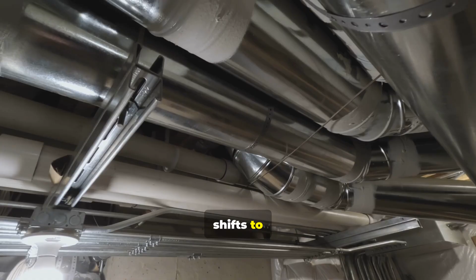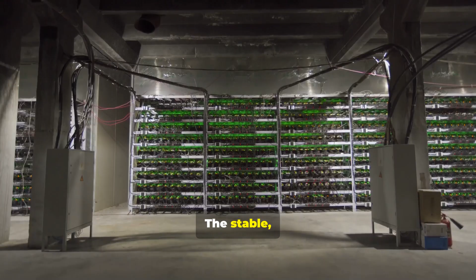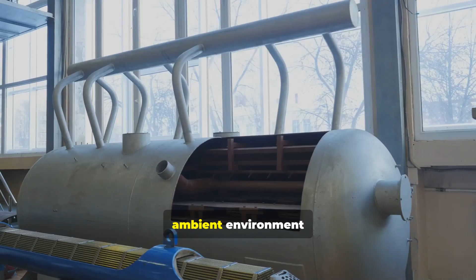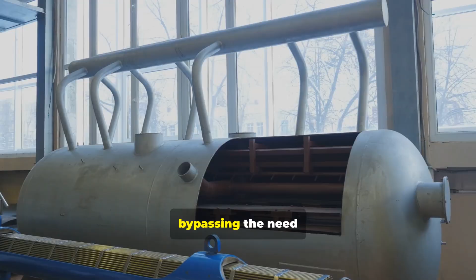That deep rock advantage is the starting point for the remarkable energy efficiency these Finnish data centers achieve, turning major cost into a manageable, predictable engineering task. The stable, low temperatures of the granite caverns enable the widespread use of a highly efficient technique known as free cooling. This method utilizes the naturally cool ambient environment to chill the water used in the data center's cooling loops, bypassing the need for energy-hungry mechanical chillers for most of the year.